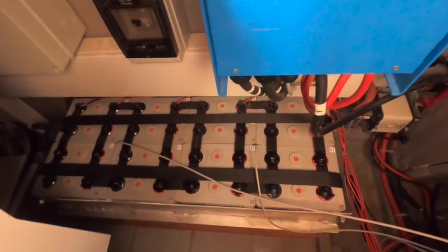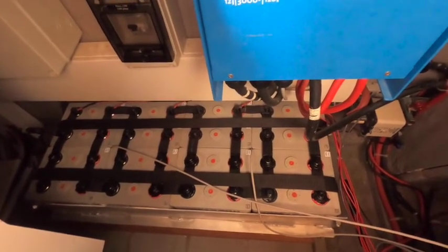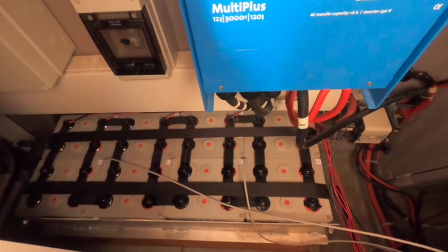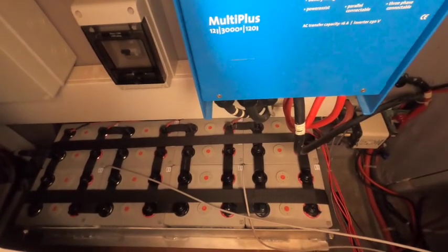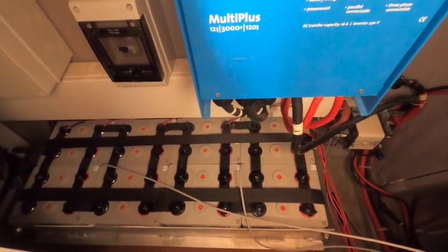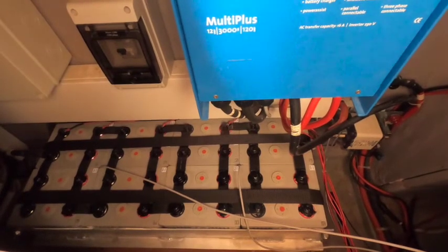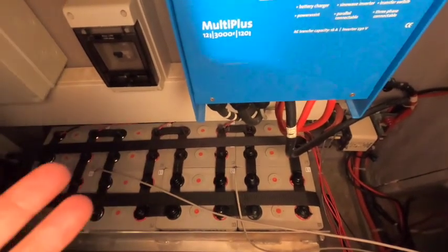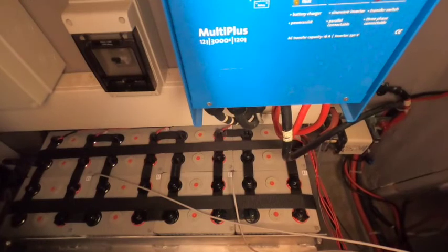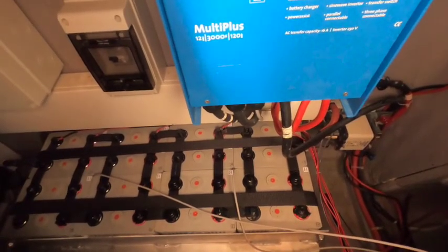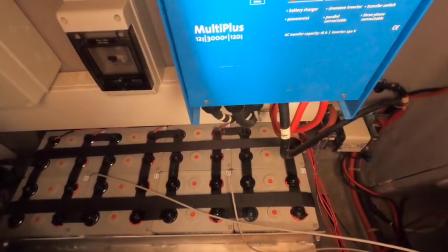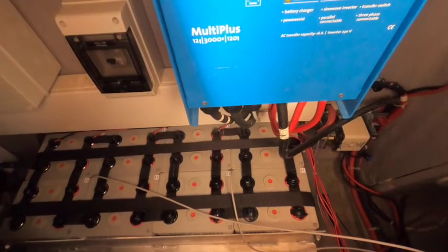So we've got 720 ampere hours at 12 volts, well 13 and a bit volts, of lithium, whereas we had 700 ampere hours of AGM before. But with the AGMs you can only really discharge them about 50%. With lithium you can take them down to somewhere around 10%, no problem, so that's effectively doubled our capacity.